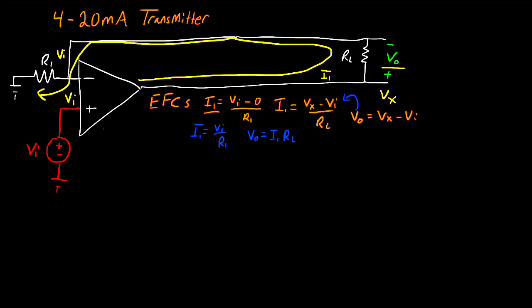So now what's normally done with a 4 to 20 milliamp transmitter is VI is set between 1 and 5 volts, and R1 is set to equal 250 ohms. Now plugging this into our I1 equation, 1 volt divided by 250 ohms gives you 4 milliamps, and 5 volts divided by 250 ohms is equal to 20 milliamps. So this sets the range that our 4 to 20 milliamp transmitter works at.